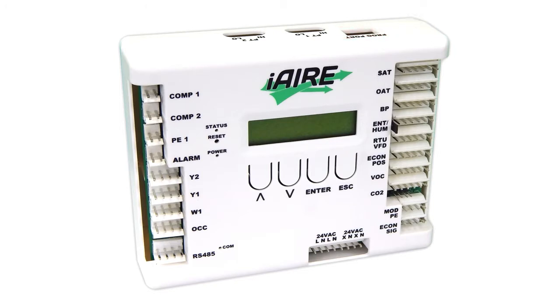The controller can have 2 board-mounted pressure transducers installed. Access to the pressure ports is located on the top of the unit if these transducers are installed. The control board is conformal coated on both sides to help prevent water from getting on the board and causing any issues with the controller.